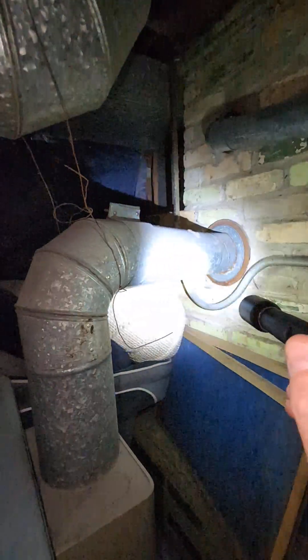That's your blower box. This is your draft hood, and that's where the pipe connects to the heat exchanger. This is where a lot of times I'll find scorching around these areas — this actually looks pretty good. And then it obviously goes out to the chimney and up and out. So it's a very basic system.